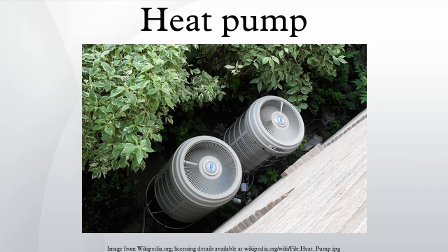Closed-loop soil or ground heat exchangers tend to accumulate cold if the ground loop is undersized. This can be a significant problem if nearby groundwater is stagnant or the soil lacks thermal conductivity, and the overall system has been designed to be just big enough to handle a typical worst-case cold spell, or is simply undersized for the load. One way to fix cold accumulation in the ground heat exchanger loop is to use groundwater to cool the floors of the building on hot days, thereby transferring heat from the dwelling into the ground loop.